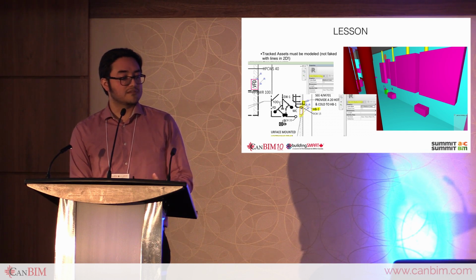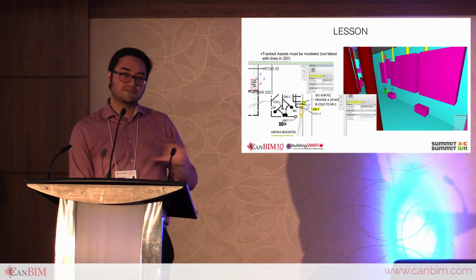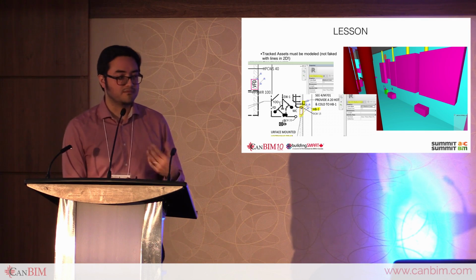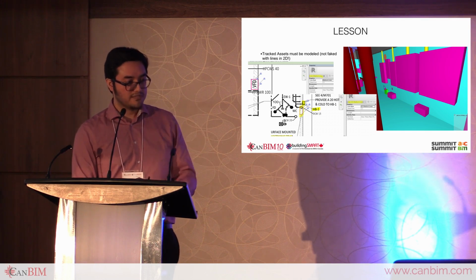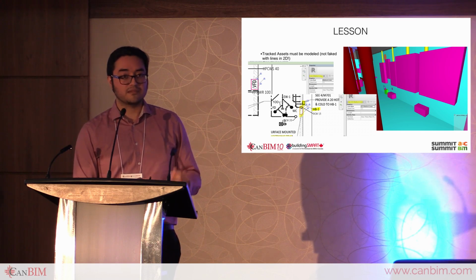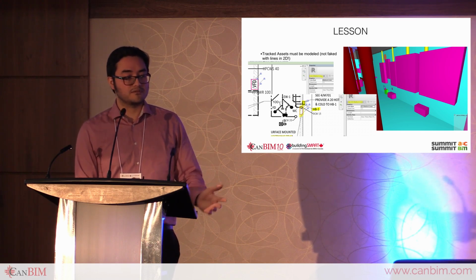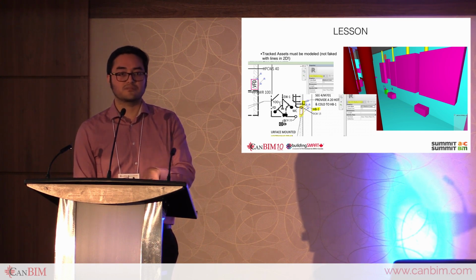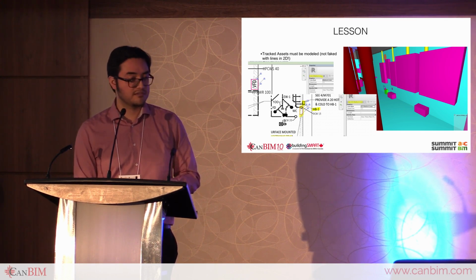And then when they eventually got modeled, you can see on the right side, there wasn't enough room because there were already electrical panels. So then they just stuck them on the bottom horizontally, which is actually not how VFDs are installed. They're installed vertically. This highlights again that this needs to happen very early, because if you don't model things, these will lead to issues. And this is why we're not getting the benefits at the end for a project.